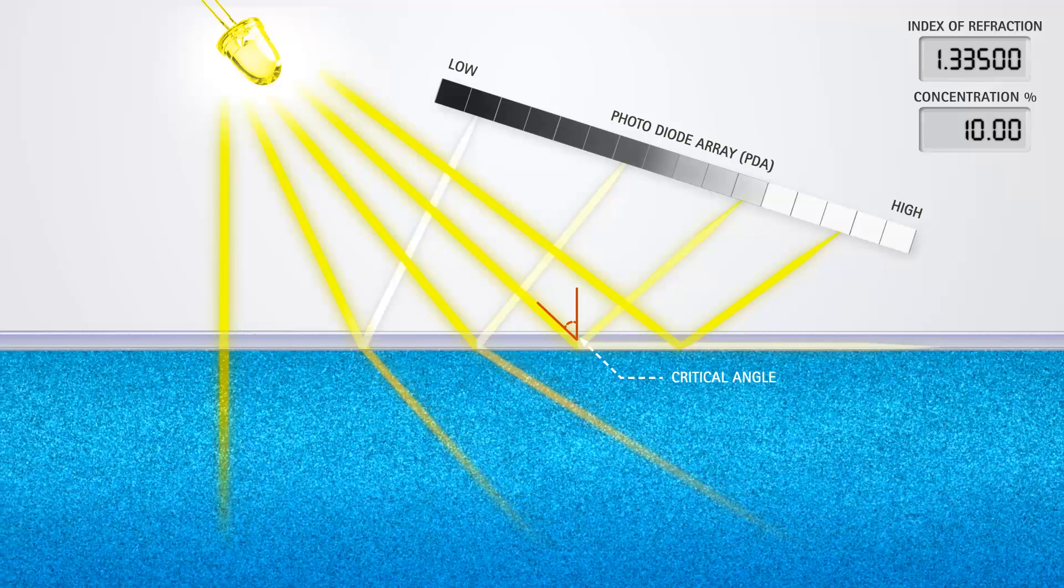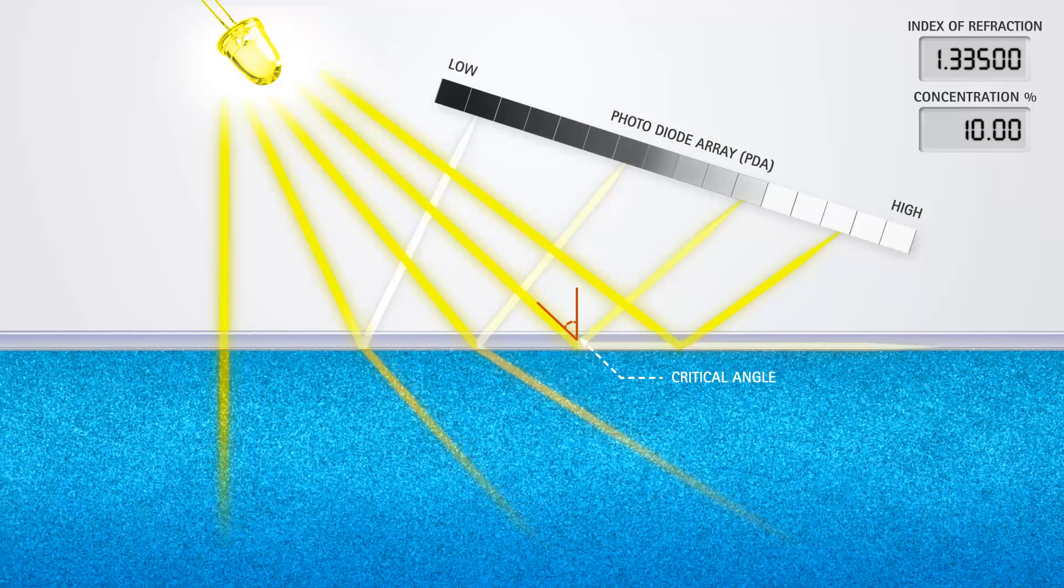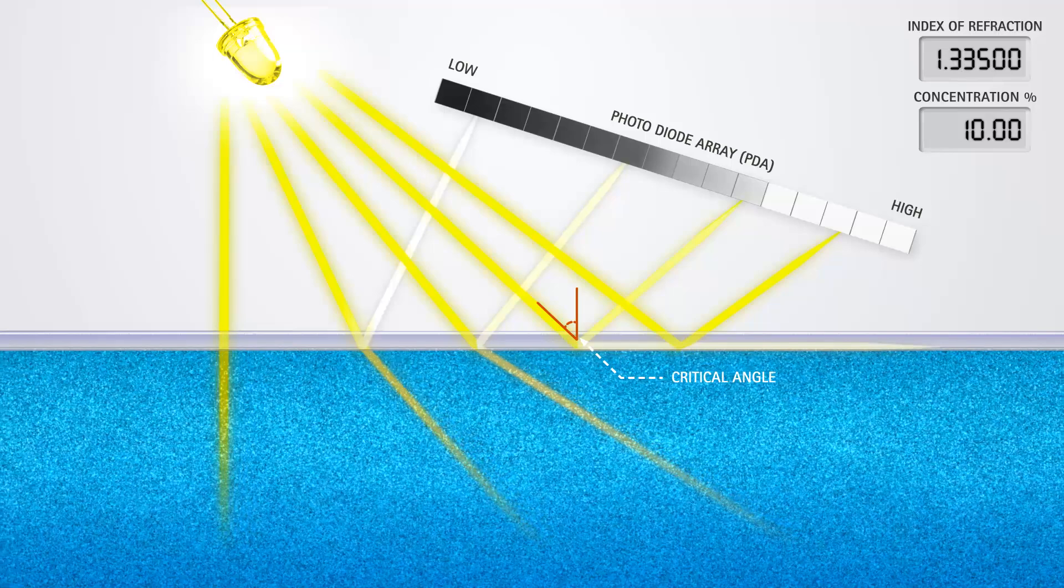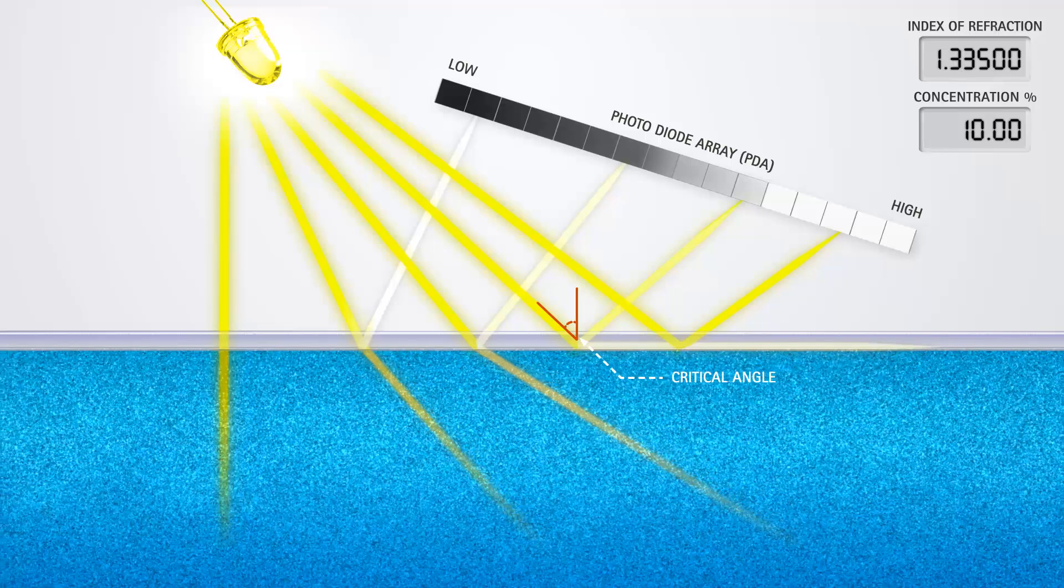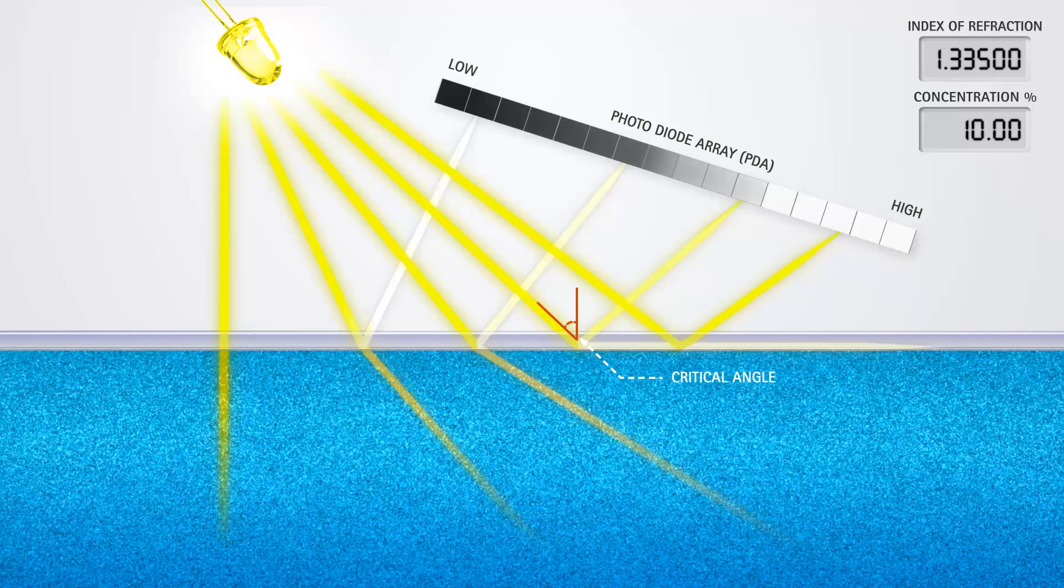Additionally, because Index of Refraction changes with fluid temperature, a thermistor monitors the temperature and the software compensates the Index of Refraction in real time.